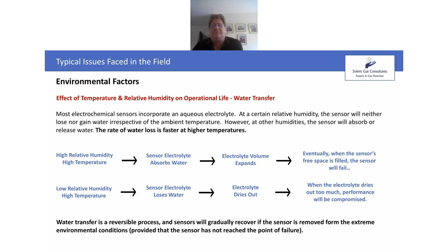At low humidities, the opposite will happen. The electrolyte will lose water, and eventually the electrolyte will dry out to the extent where the sensor will fail. Now, usually you'll find that if you're using these in extreme humidities, you will get the moisture transfer, but if you put the sensor back into better conditions, it will tend to recover over time.